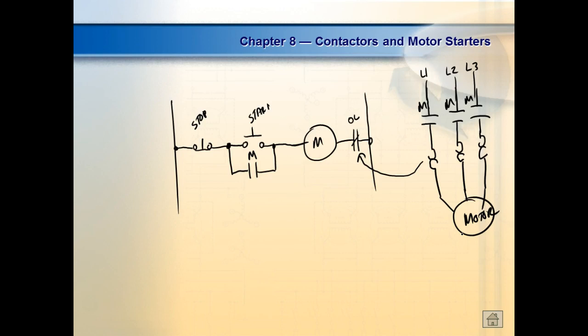So like I said, on some motors the overloads are internal. But any motor that's got that on the nameplate, it should say thermally protected, which means the overloads are inside the motor. If it doesn't say thermally protected, that means that motor might not be protected against overloads. And if that motor ever stalls, what could happen? It could burn itself up, right? Maybe catch a fire. Everybody okay there? So the only thing between L2 and the load is the overload contact. These are only going to be for motor starters. So contactors won't have overload contacts, and control relays won't have overload contacts. Only motor starters will have overload contacts.